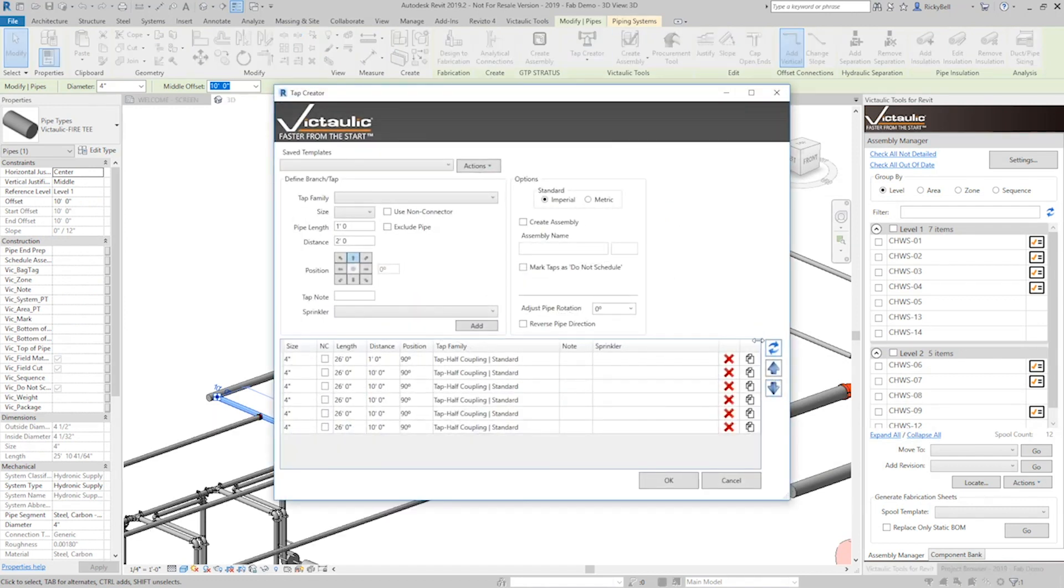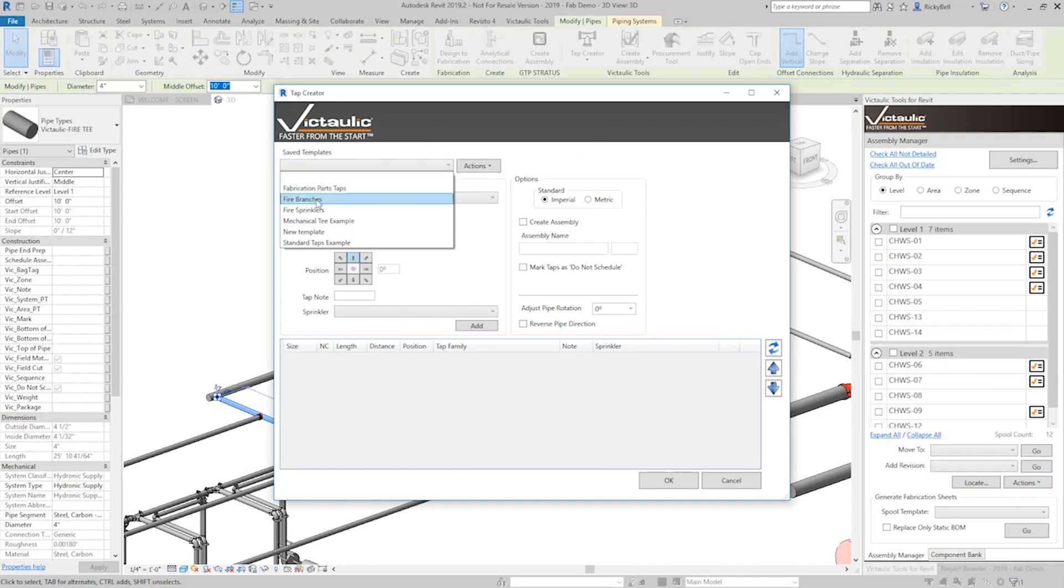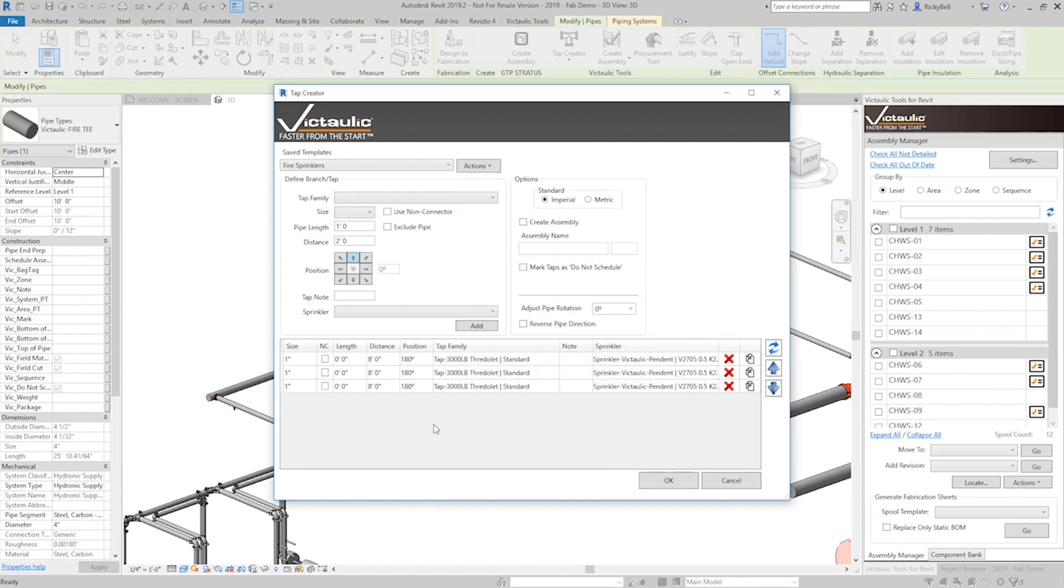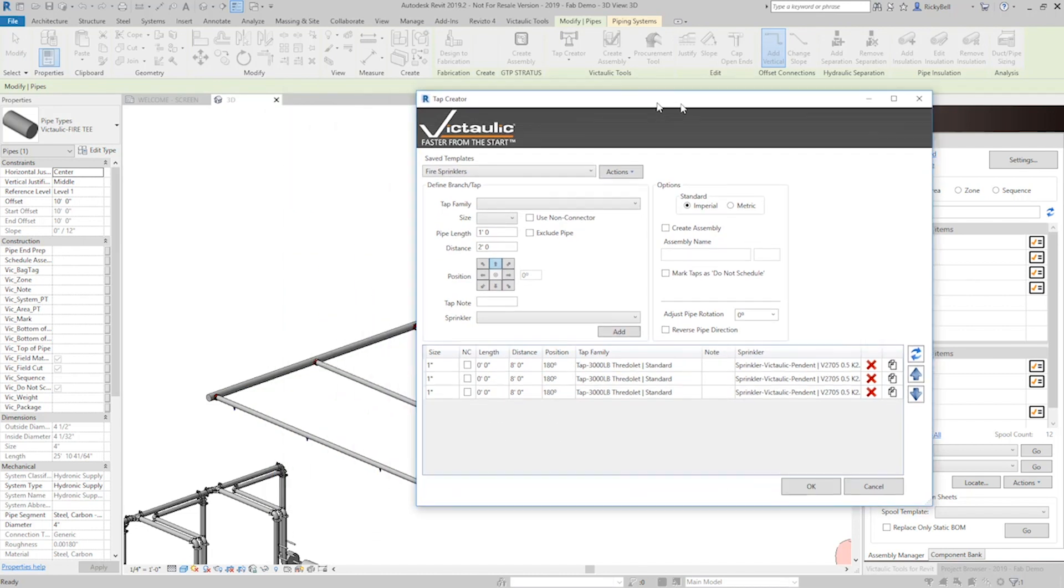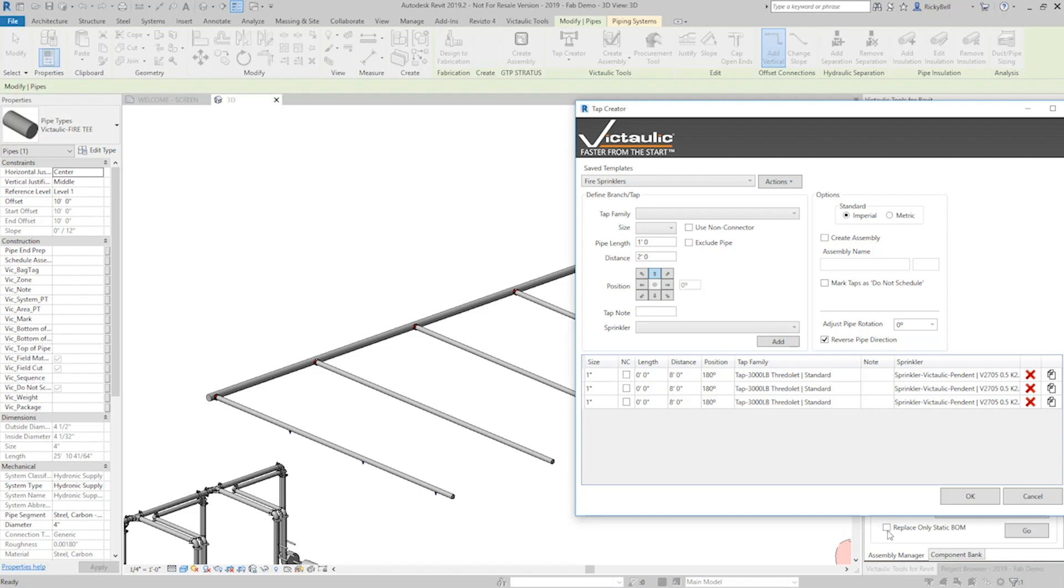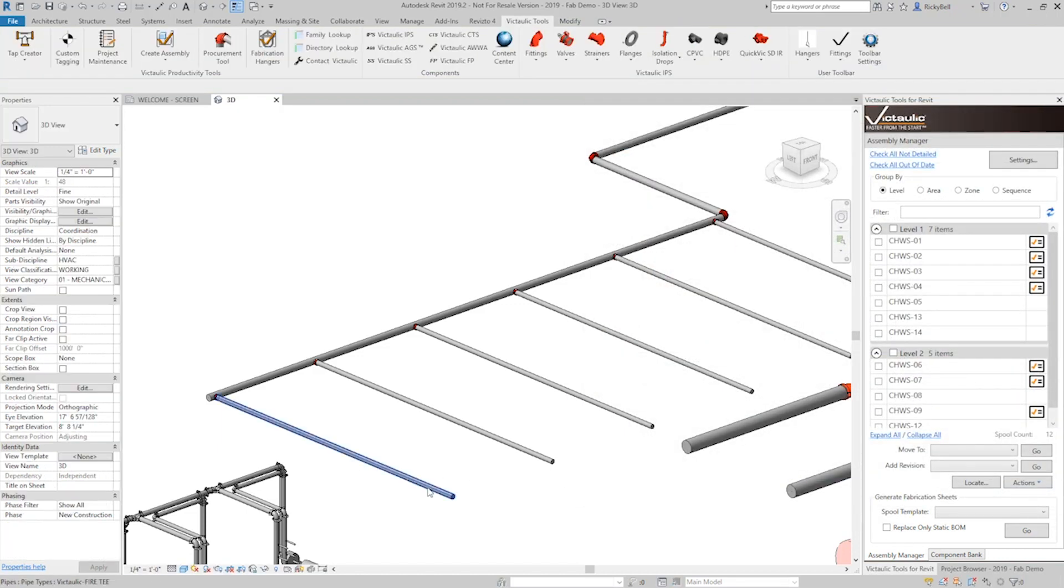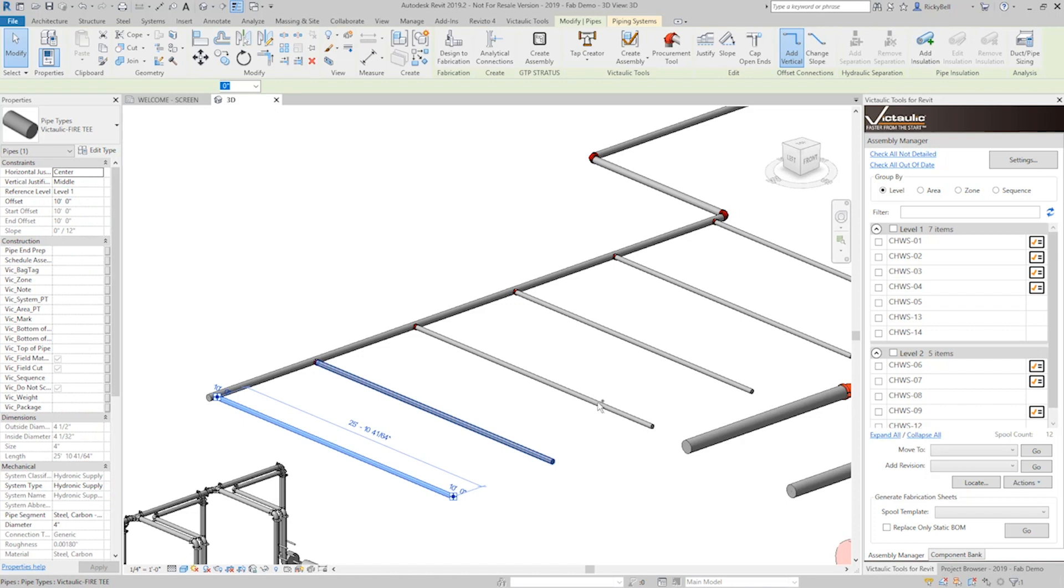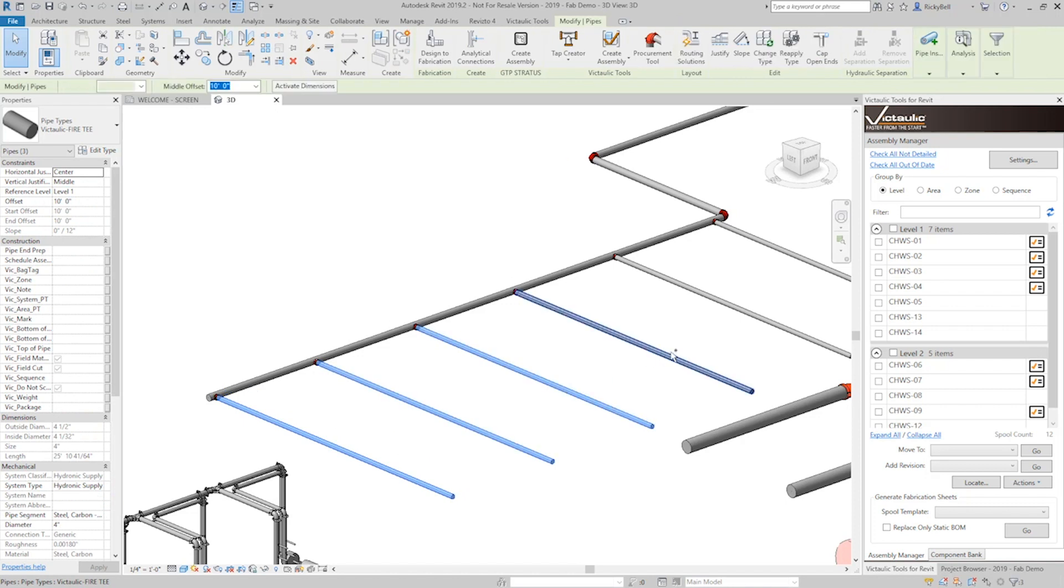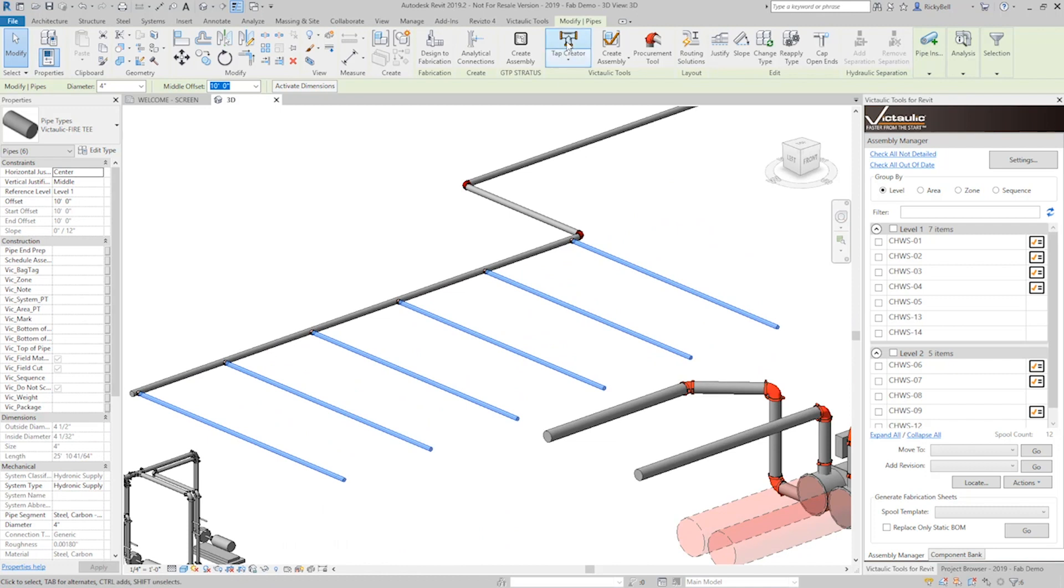Now if I wanted to put sprinklers on there I can highlight one of these branches, open the tap creator, clear out what's already in there, or just recall what I made called fire sprinklers which is going to place a sprinkler every eight feet along this line right here. You can see it kind of started at the wrong end. You can always click on reverse pipe direction and the eight feet will then start from the main side. So now that we've got this configured, I'm going to hit cancel here and I'm going to select all of these branches that were just created and I'm going to place some sprinklers on there.